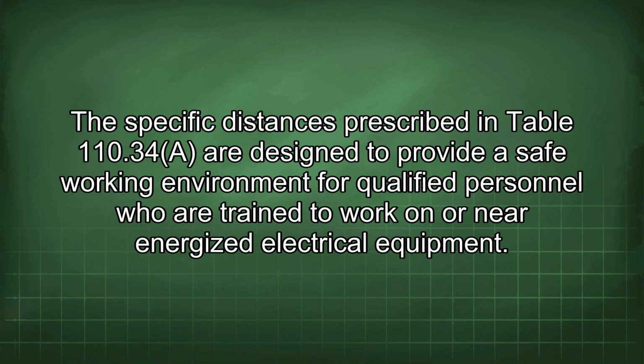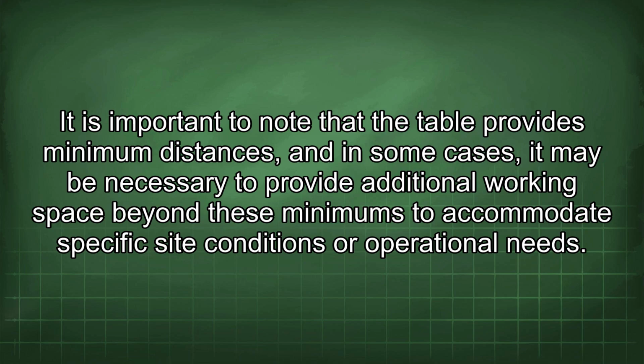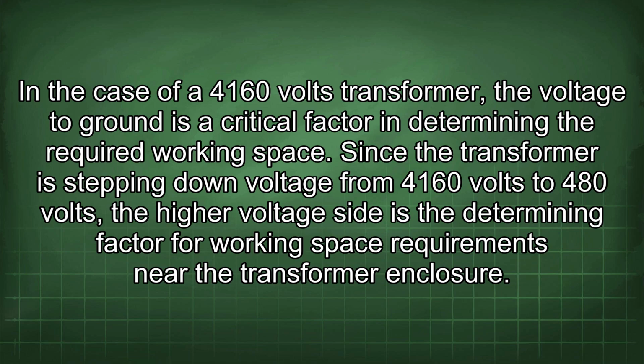The specific distances prescribed in Table 110.34 are designed to provide a safe working environment for qualified personnel who are trained to work on or near energized electrical equipment. It is important to note that the table provides minimum distances, and in some cases, it may be necessary to provide additional working space beyond these minimums to accommodate specific site conditions or operational needs. In the case of a 4160 volts transformer, the voltage to ground is a critical factor in determining the required working space.